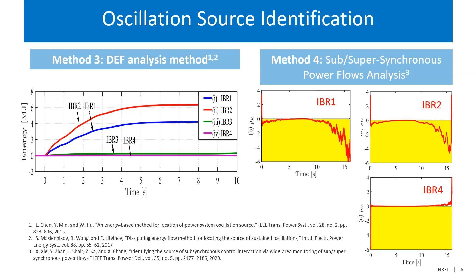By now, we already understand that IBR 1 and 2 may be suspicious, but what caused this oscillation is still unknown. That's why we started to develop these EMT models with two purposes. One, we need to recreate these 19 Hertz oscillations so we know what happened there. Second, we want to propose and test mitigation methods using this model.